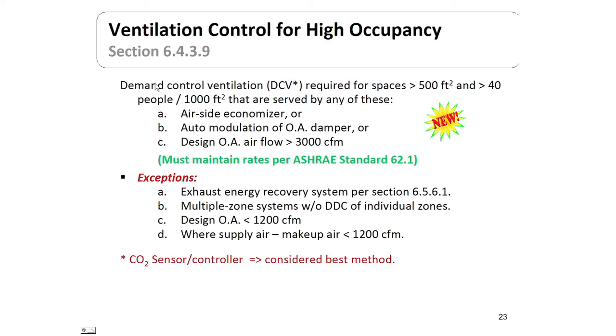Demand control ventilation (DCV) is required for spaces greater than 500 square feet with greater than 40 people per 1,000 square feet — that's why it's called ventilation control for high occupancy. It's also required if the building is served by an air-side economizer, if you modulate an outdoor air damper, or if your design airflow is greater than 3,000 CFM. One important note: in maintaining ventilation control, you must not violate ASHRAE Standard 62.1, which mandates certain outdoor air requirements for indoor air quality and health.